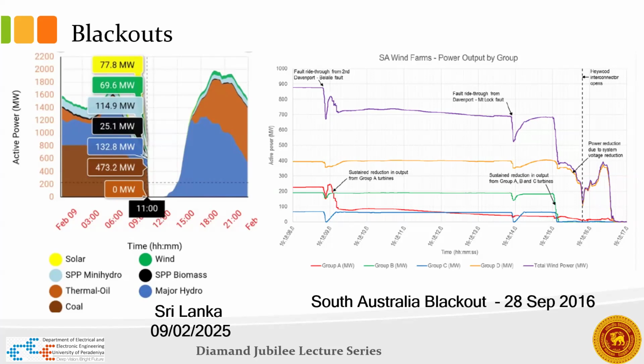The wind turbines came with a default setting of 2 ride-throughs, and nobody checked that. So it was only set to operate for 2. If you look at the South Australian grid codes, it says 8 consecutive ride-throughs. That was just a setting they had to configure in their controllers, but they never knew it came with 2 by default, which triggered an issue against the grid code.